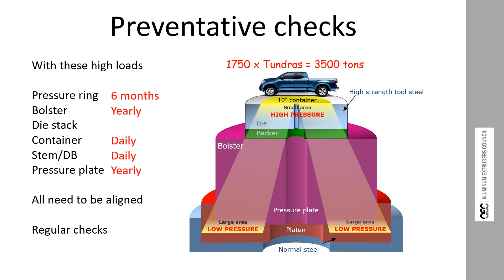So, preventative checks. I refer you to the webinar on the AEC library that Chris Jarrett and I did a few years ago, specifically on alignment, so I won't repeat too much. The recommendation was that the pressure ring in the platen should be checked for flatness every 6 months, and you should have a tolerance. Al Kennedy's website has all sorts of numbers on what these tolerances should be.